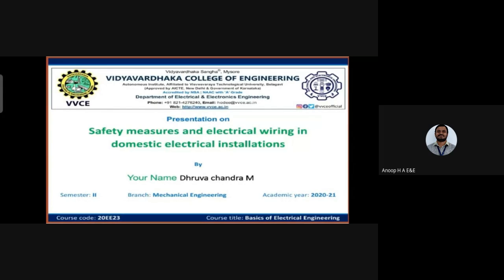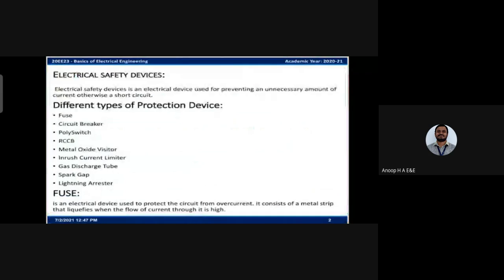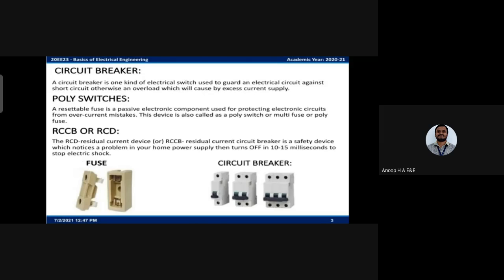The topic of today, which I am going to present to you all, is safety measures and electrical wiring in domestic electrical installations. Electrical safety devices are devices used for preventing an unnecessary amount of current flow. Types of protection devices are: fuse, a device used to protect the circuit from overcurrent; circuit breaker, an electrical switch used to guard an electrical circuit against short circuits; poly switch, a passive electronic component used for protecting electronic circuits from overcurrent faults; RCCB or RCD, a device that notices a problem in the home power supply, then turns off in 10 to 15 milliseconds to stop electric shocks.